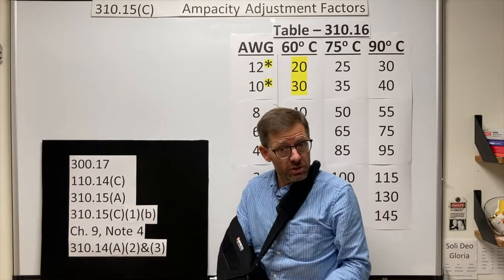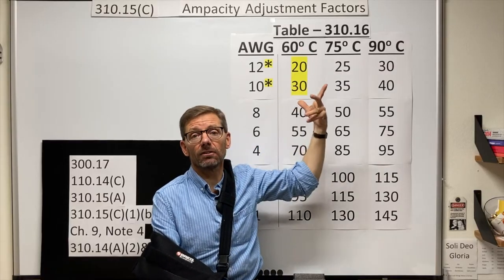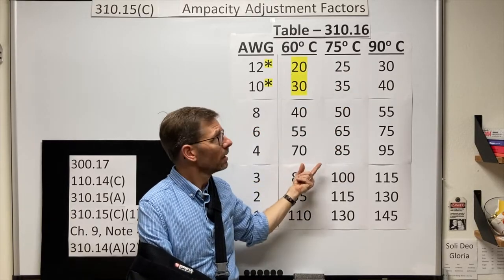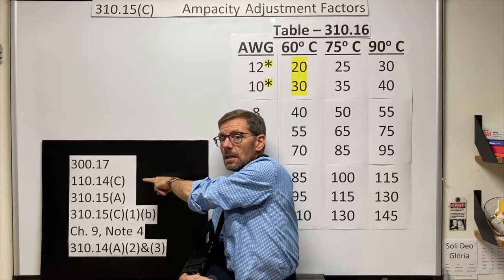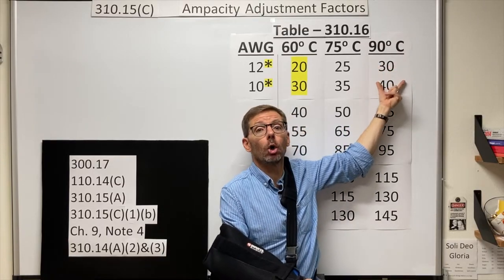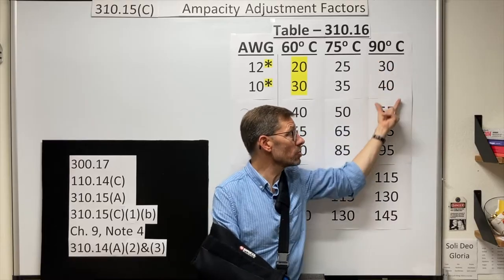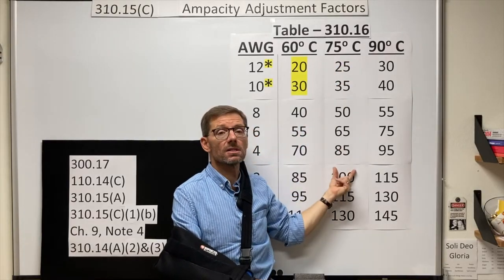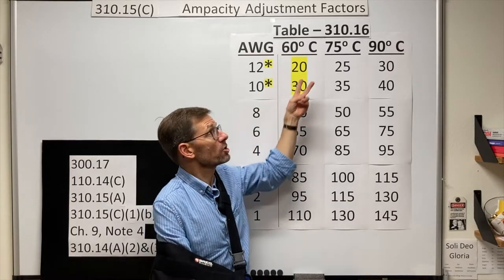110.14(C) also restricts us to the ampacities in the column with the lowest temperature rating of any connected equipment. So we know we're often restricted to these amperages or these, but a lot of our conductors are rated for 90 degrees Celsius. Now it's the second sentence here, or the second paragraph here, that allows us to use the conductor's own ampacity based on its insulation rating. So if I have a 90 degree rated insulation, I can use these ampacities to start my calculation. 75 degree rated conductor, these ampacities to start the calculation, as long as I don't end up higher than what my restrictions are for the connected equipment.